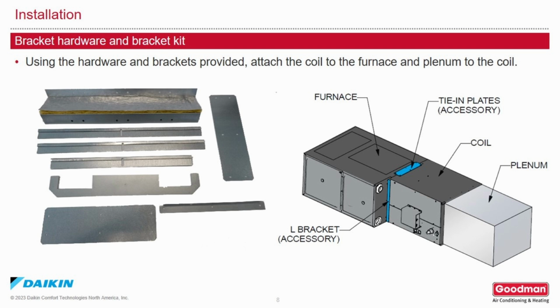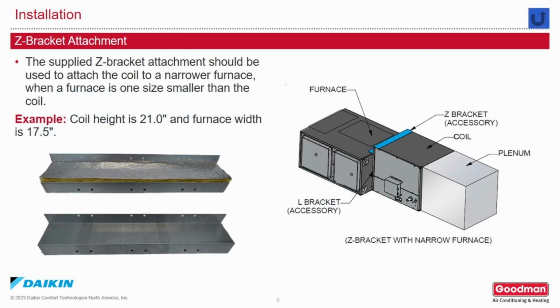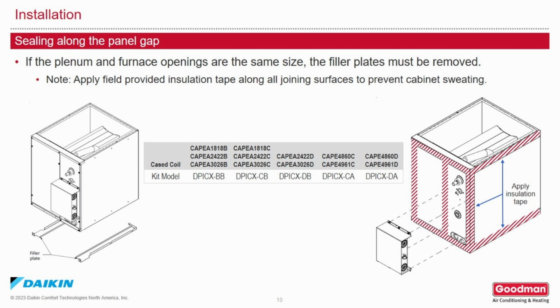Using the hardware and brackets provided, attach the coil to the furnace and the plenum to the coil. The supplied Z-bracket attachment should be used to attach the coil to a narrower furnace when the furnace is one size smaller than the coil. For example, if the coil is 21 inches wide and the furnace is 17.5 inches wide. If the plenum and the furnace openings are the same size, the filler plates must be removed.